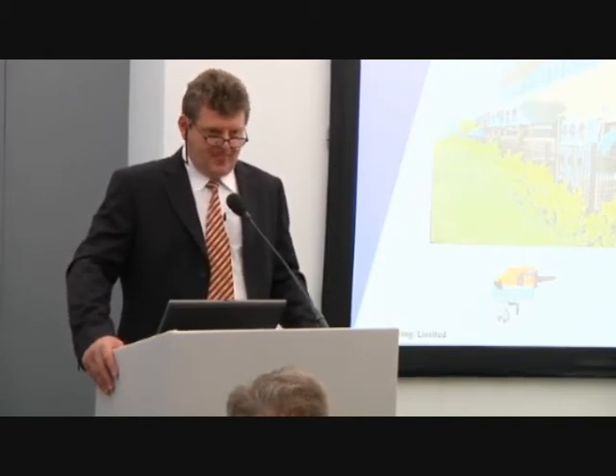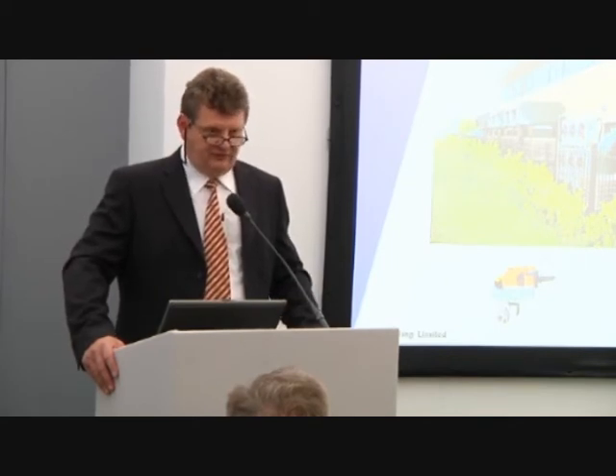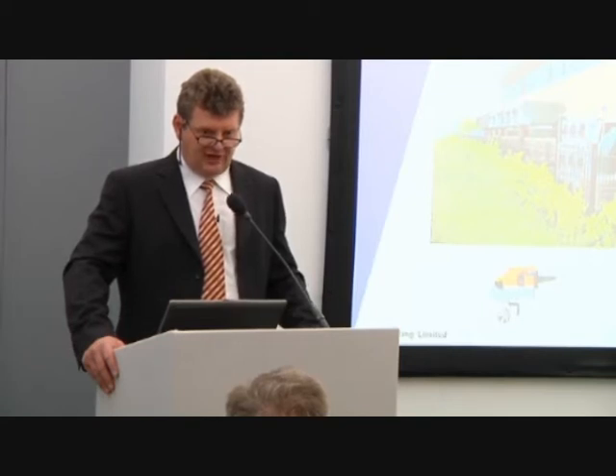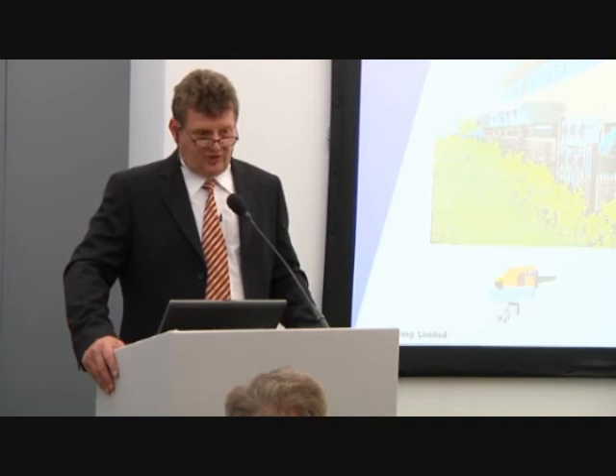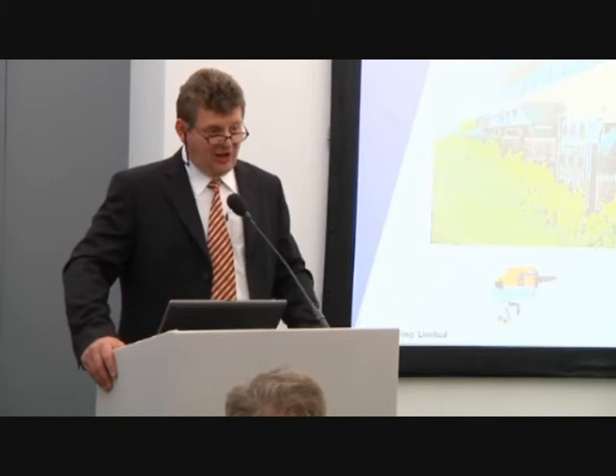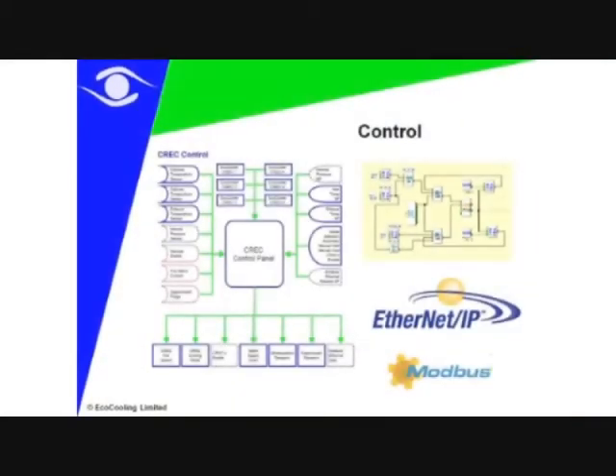It also gives us a control measure. If something fails that we haven't been able to pick up automatically or electronically, the pressure will drop, the system will see the pressure drop, and all the other cooling systems and their fans will ramp up their speed accordingly and raise an alarm condition. All this is linked together through what we call our CREC control panel.